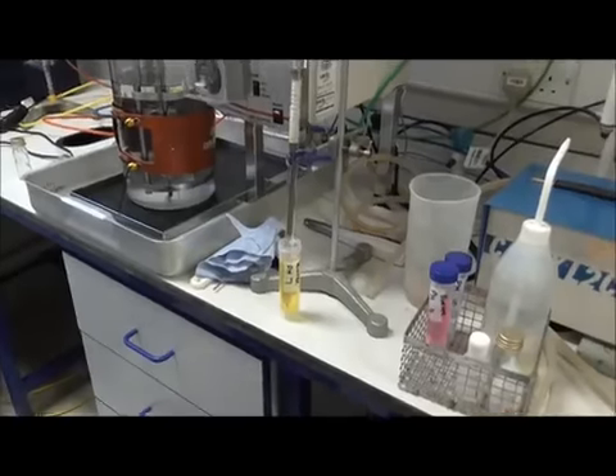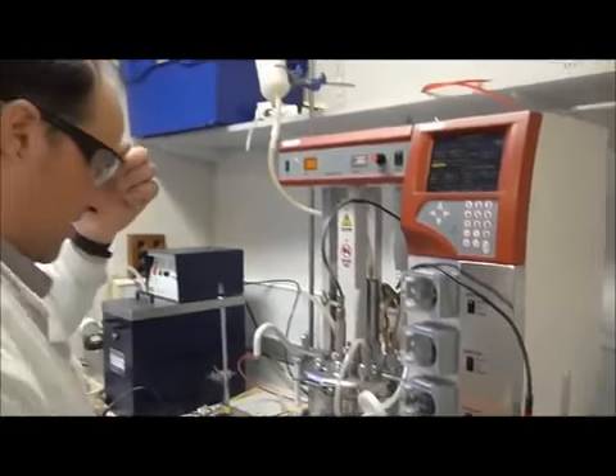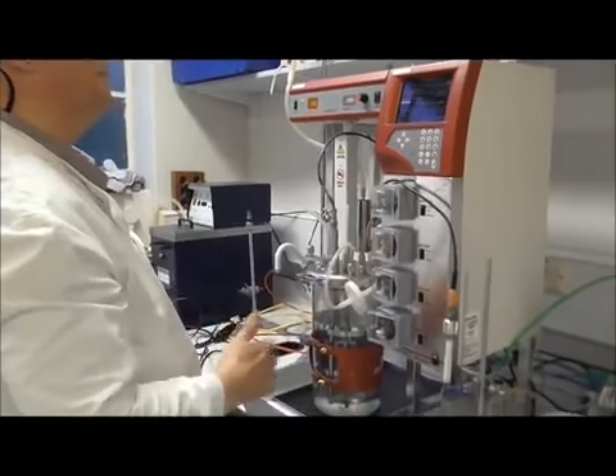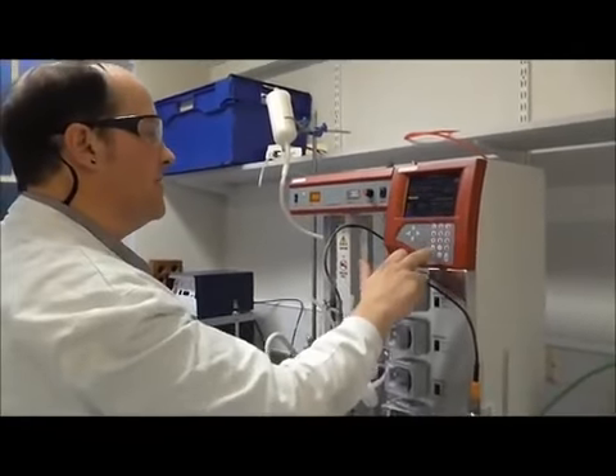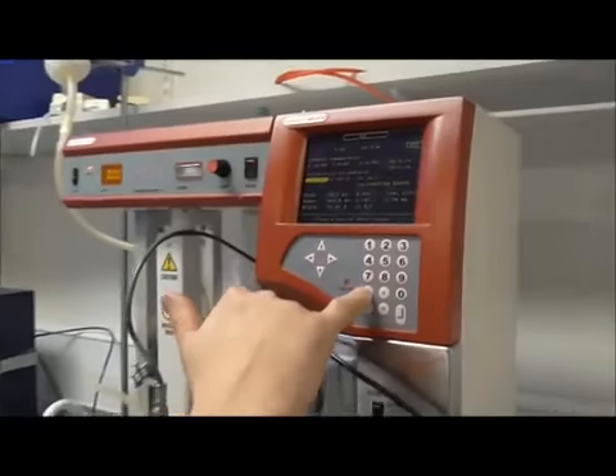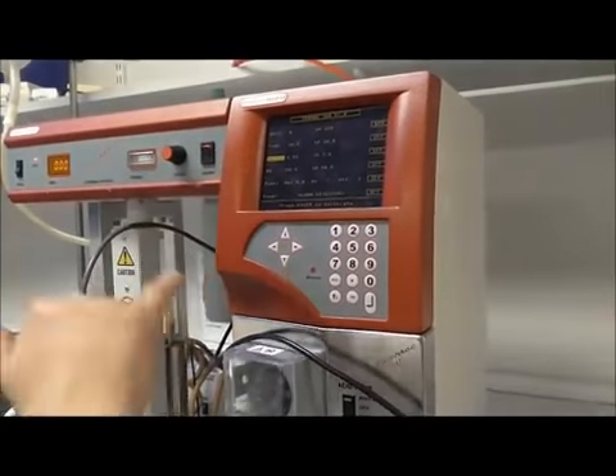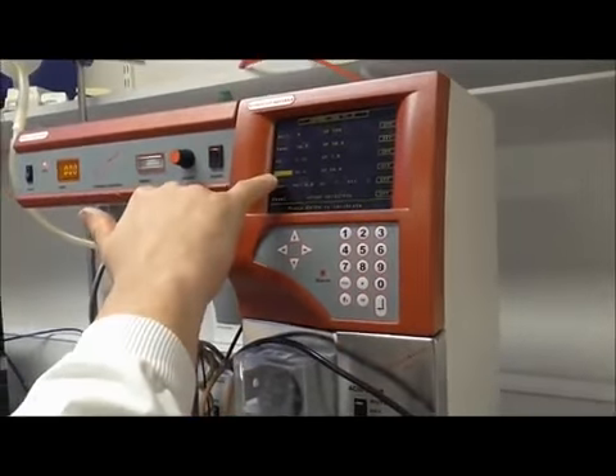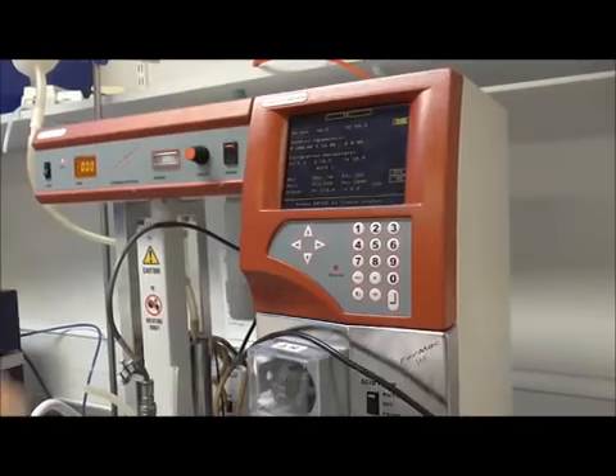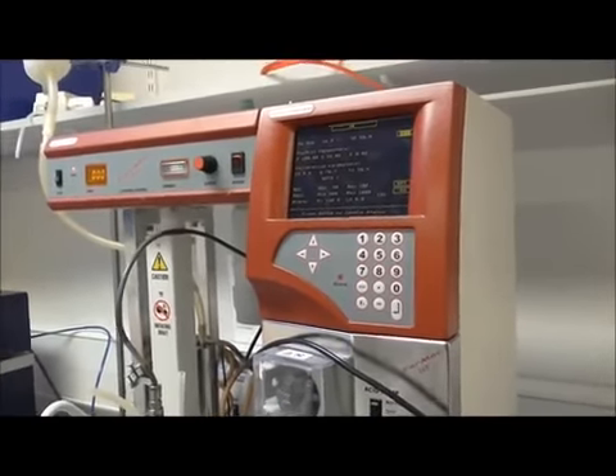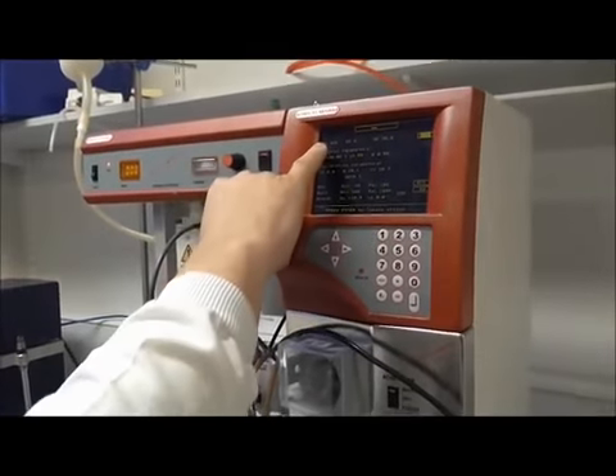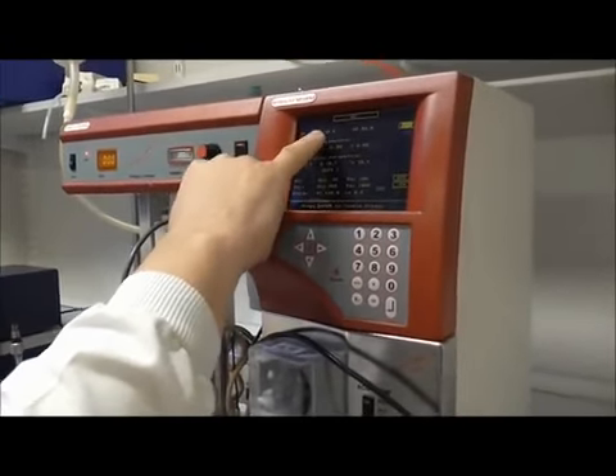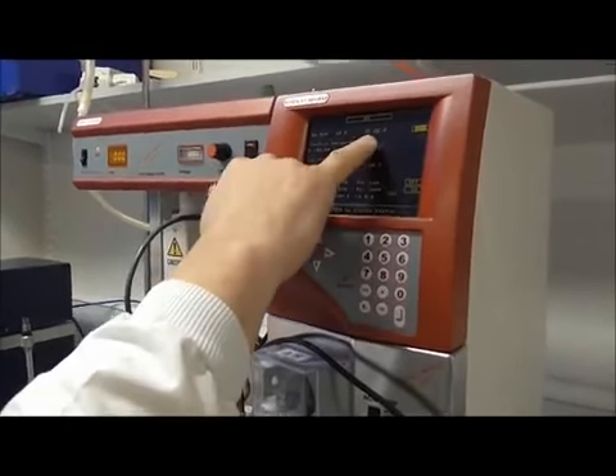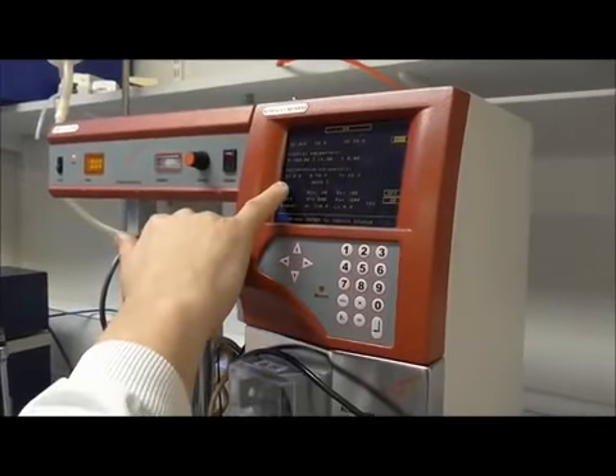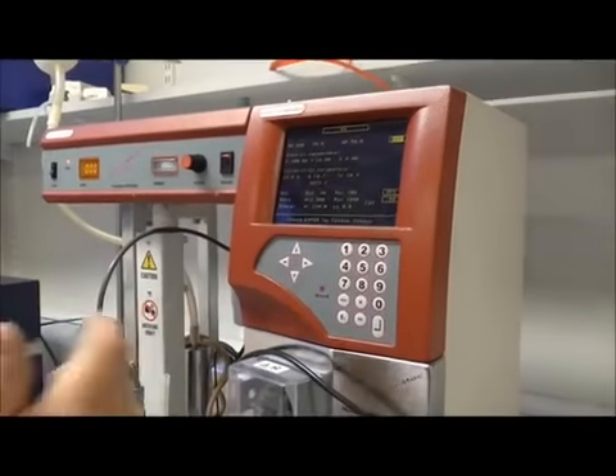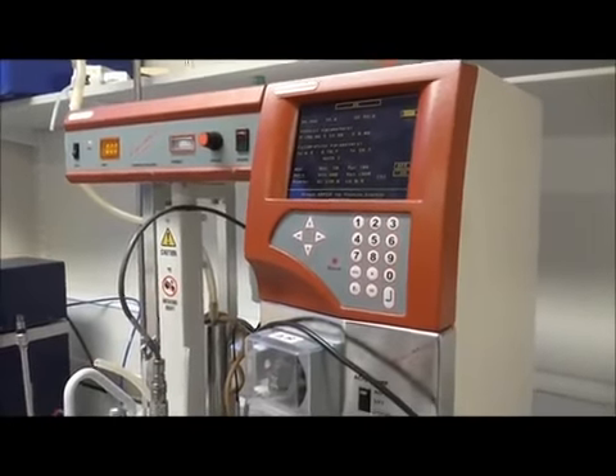Right, on to dissolved oxygen. We do this in situ. The probe stays in the vessel, so we escape from the pH calibration menu by pressing escape. Back to the main menu, we scroll down to DO, dissolved oxygen, we press enter, and we have our dissolved oxygen calibration menu. So we have our electrical readout here, nanoamps, our actual percentage, our set point, we have our PID terms here, and our calibration parameters there. So we need to get this oxygenated.